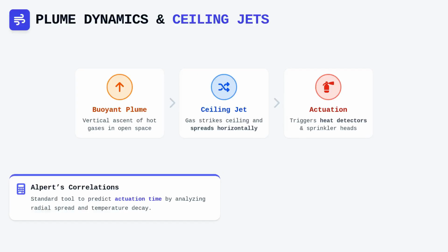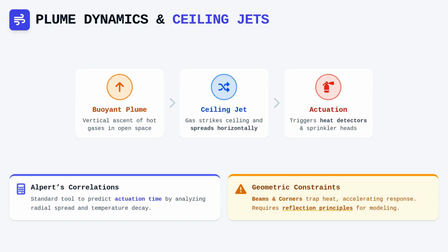Alpert's correlations remain the standard tool for predicting the time to actuation, as they account for the radial spread of the hot gas layer and the subsequent decay in temperature and velocity as the gas moves further from the stagnation point. We must be particularly careful to adjust our calculations when these flows are interrupted by geometric constraints like wall corners or beams, which can artificially trap heat and accelerate activation times compared to a wide open area. The physics remains consistent, but the boundary conditions require us to use reflection principles to model the flow properly. Failure to account for these constraints often leads to underpredicting the response time of detection systems.